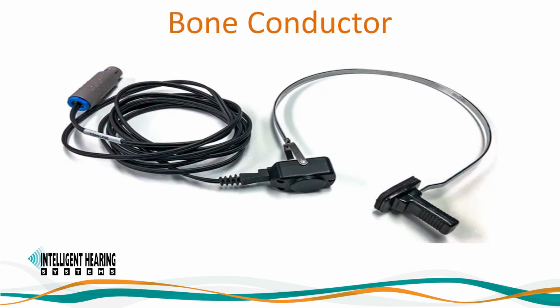Keep electrodes plus their leads away from the bone vibrator and its cables. Use practical positioning that will not diminish response, particularly important for recording the cochlear microphonic. When testing by bone conductor, the vibrator should be above the level of the mastoid electrode. If there's no response when expected, it is worth checking the vibrator placement.